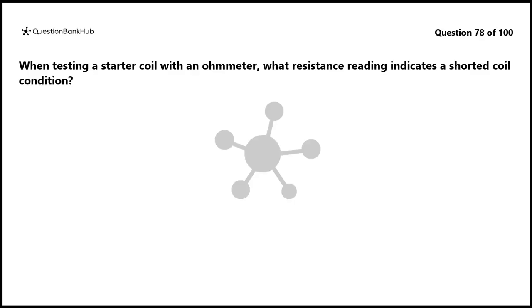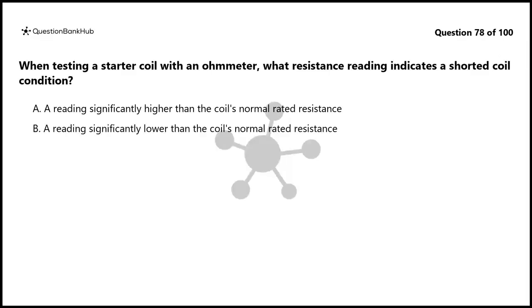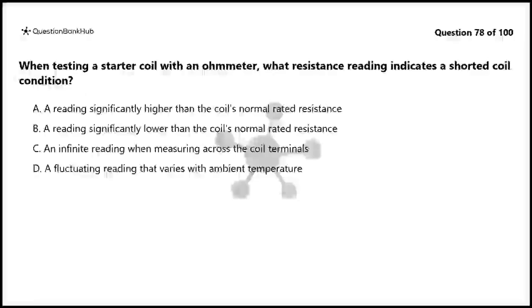Question 78. When testing a starter coil with an ohm meter, what resistance reading indicates a shorted coil condition? A. A reading significantly higher than the coil's normal rated resistance. B. A reading significantly lower than the coil's normal rated resistance. C. An infinite reading when measuring across the coil terminals. D. A fluctuating reading that varies with ambient temperature.